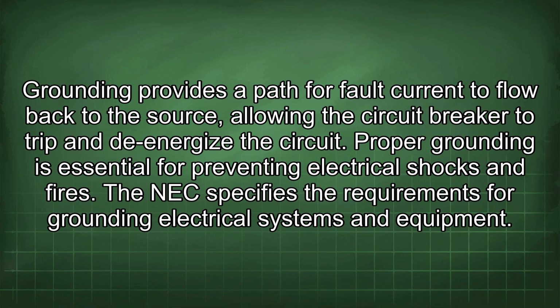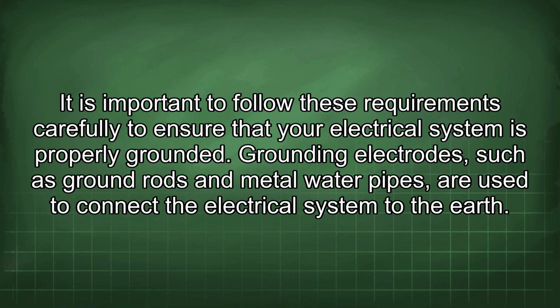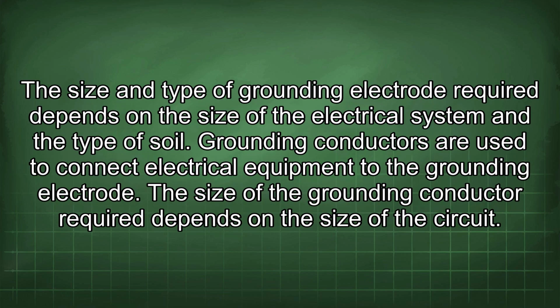The NEC specifies the requirements for grounding electrical systems and equipment. It is important to follow these requirements carefully to ensure that your electrical system is properly grounded. Grounding electrodes, such as ground rods and metal water pipes, are used to connect the electrical system to the earth. The size and type of grounding electrode required depends on the size of the electrical system and the type of soil. Grounding conductors are used to connect electrical equipment to the grounding electrode. The size of the grounding conductor required depends on the size of the circuit.